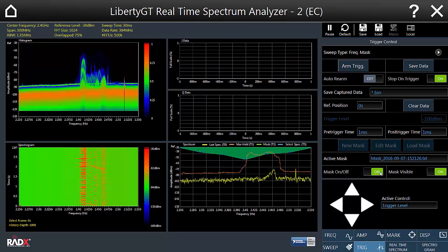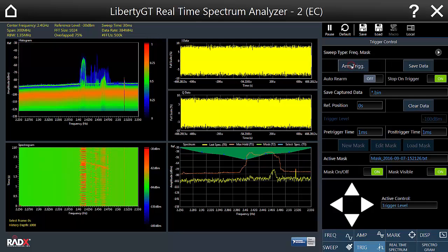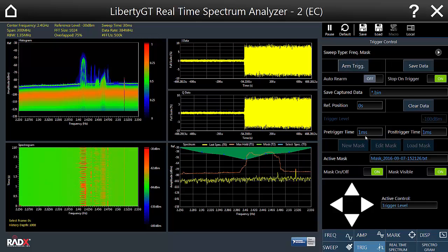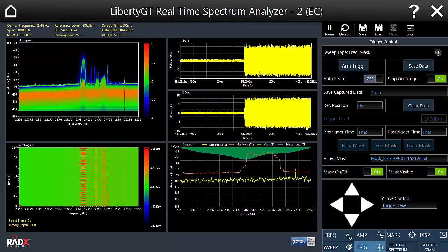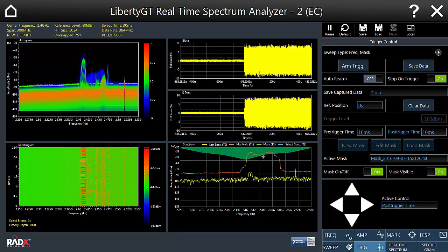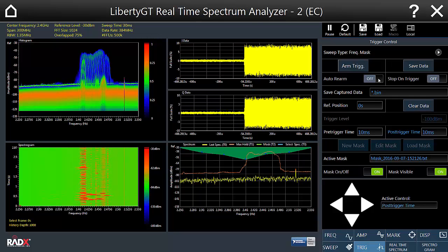Now we'll activate the mask, and as soon as we arm the trigger, whenever the signal enters the masked frequency and amplitude range we'll get a capture of the incoming samples in real-time. The maximum buffer capture size is 256 mega samples, and the buffer size is controlled with pre-trigger and post-trigger time controls. You can also observe how often the incoming signal enters the masked region by setting the triggering process to auto-rearm every time the specific trigger occurs.